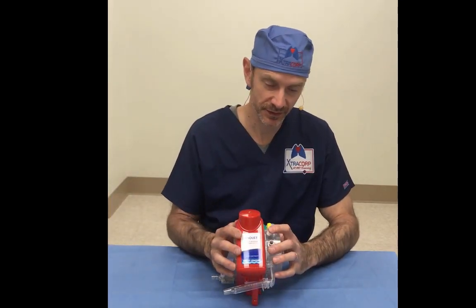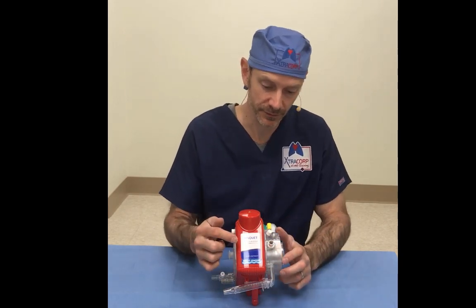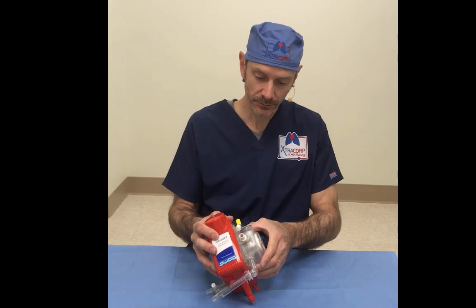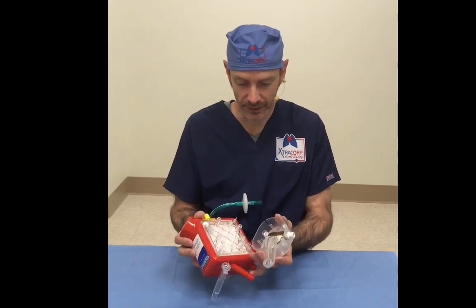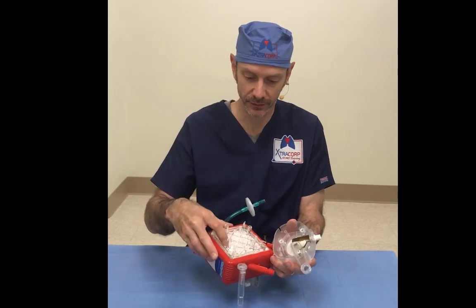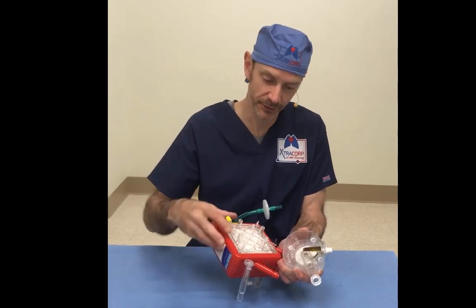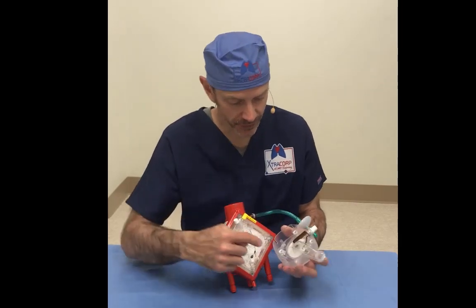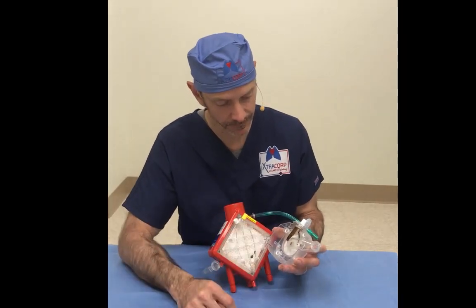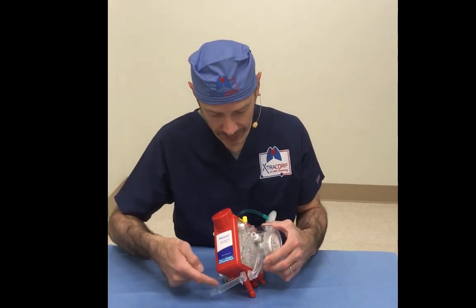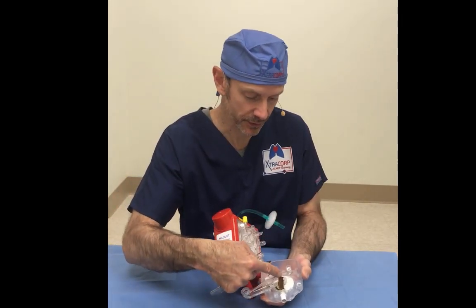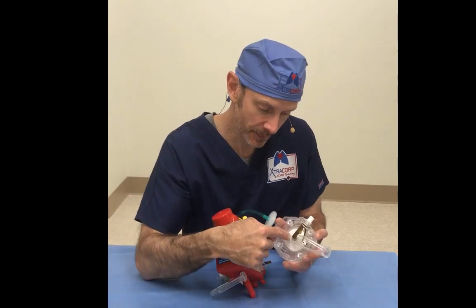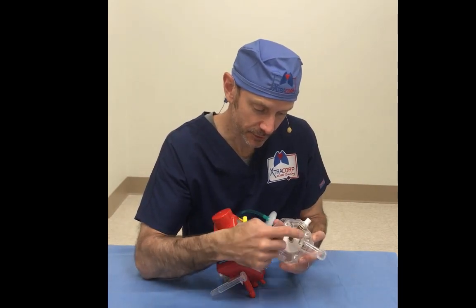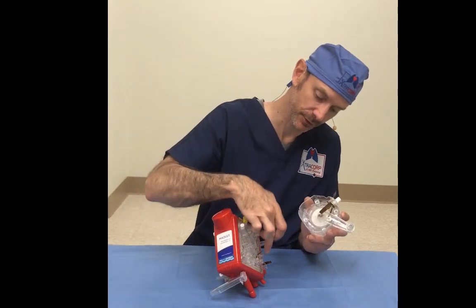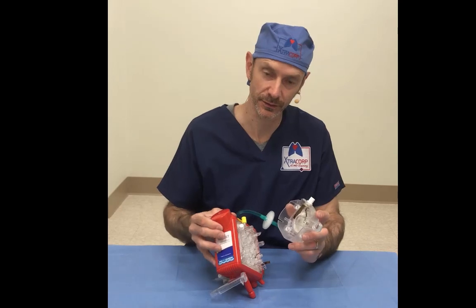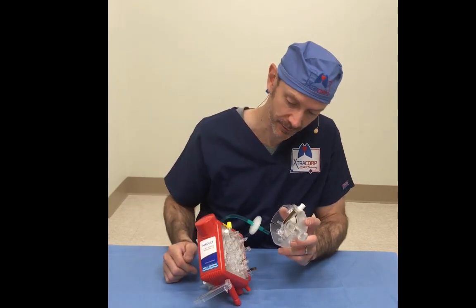Let's open this up and see what's in the internal space of the HLS set. Inside this looks like a relatively normal oxygenator, but it's got 4 channels. And those 4 channels match up with 4 outlets of this centrifugal pump. When it all comes back together again, the inlet is here. The blood goes to here, into the pump then, round and around, comes out these 1, 2, 3, 4 channels that are right here. 1, 2, 3, 4 channels into the face of the oxygenator where the blood then finally meets the fibers on the inside.